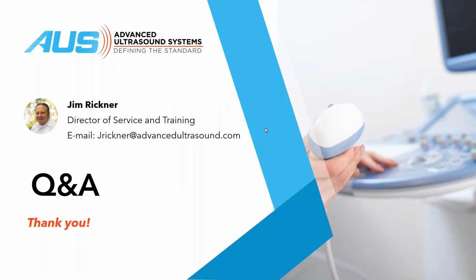I think one of the things that I find amazing is how much frequency matters. You have a probe, for example, that goes from, let's say, 2 to 5 megahertz, and you put it on a system, and you're looking at image quality, and most beginners use a single frequency. It's whatever it defaults to, and they don't realize that there are 2 other frequencies that they can dial in. By being able to change the frequency and change the focal point, they can drastically affect how the image looks. And I think once they realize just how much influence they can have over the image when they have a phantom to look at and learn to manipulate the settings, it's a real eye-opener for them.